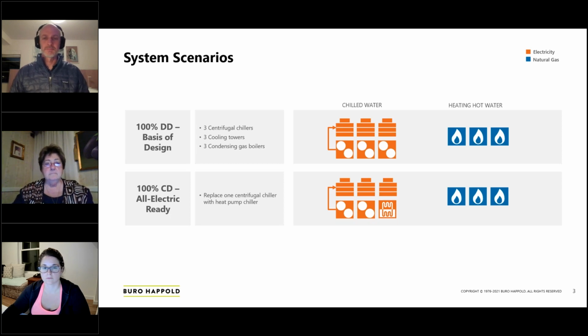And the key component to that design strategy is to replace one of the centrifugal chillers with a heat pump chiller that provides the ability to work in heat recovery mode. It also means that the size of the equipment that should be replaced later in the building's life to be all electric will be smaller and more manageable, i.e. air source heat pumps and the boilers themselves.